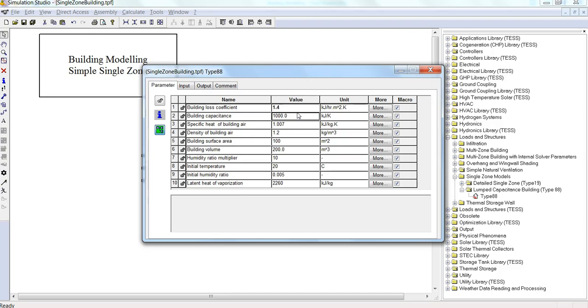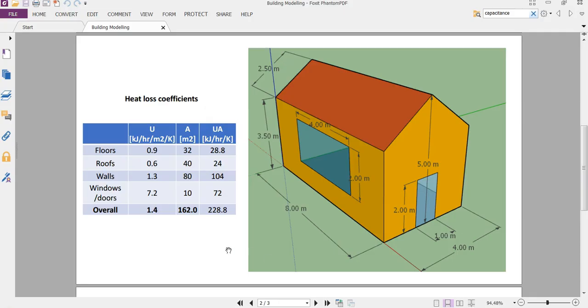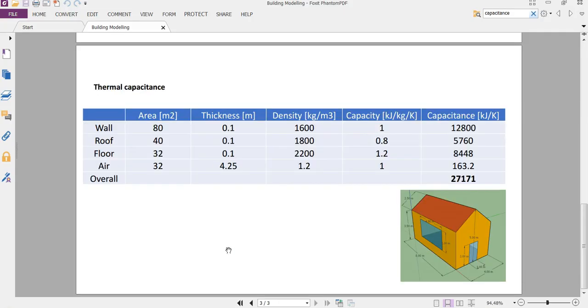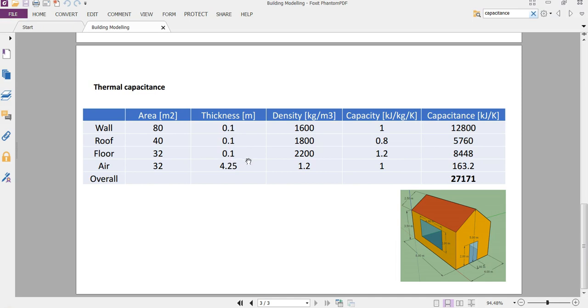And then the building capacitance. So it's a combination of all of the building surfaces as well. So we have the area for the wall, roof, and floor. And also the air will contribute a small amount of capacitance. I estimate some thicknesses for these surfaces. The thickness here I've used is the height of the building plus half of this roof area, just to make the calculation simple for the overall amount of the volume of air.